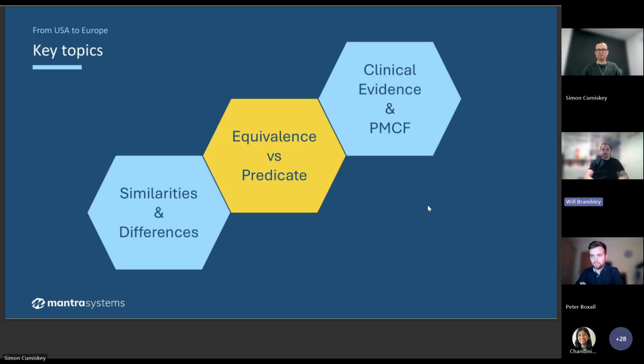In terms of risks of an equivalence claim, there are a few things you need to be confident in before you go down that route. The first one is that you're going to be able to gain adequate access to information about the equivalent device in order to demonstrate to the notified body that it is the same technologically, biologically, and clinically. If you're not able to access the information about how the equivalent device performs or its design characteristics, its specification, whether that's through direct contact with that manufacturer or information that's readily available online, then you're going to struggle to prove the equivalence between them.